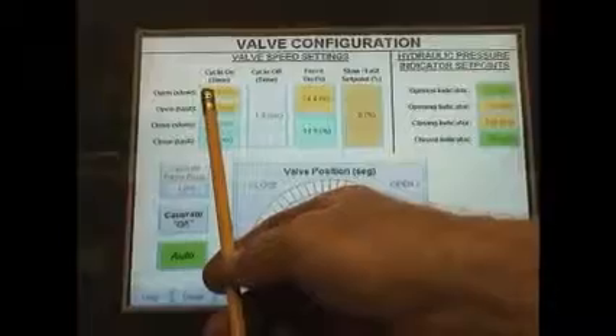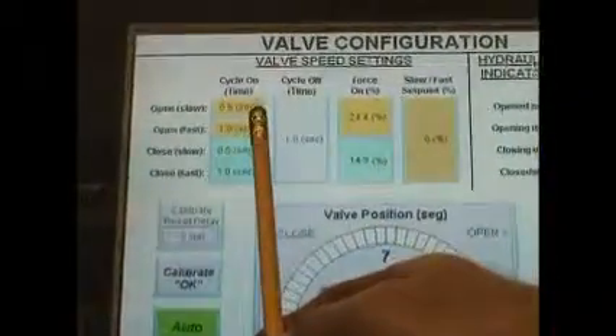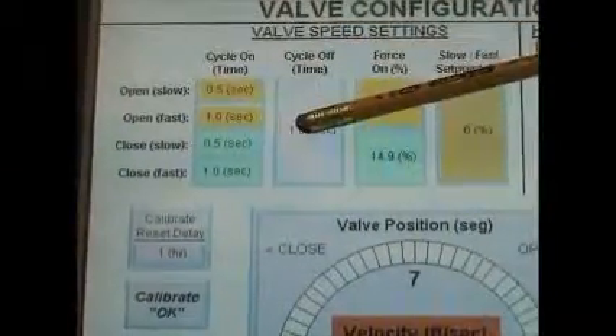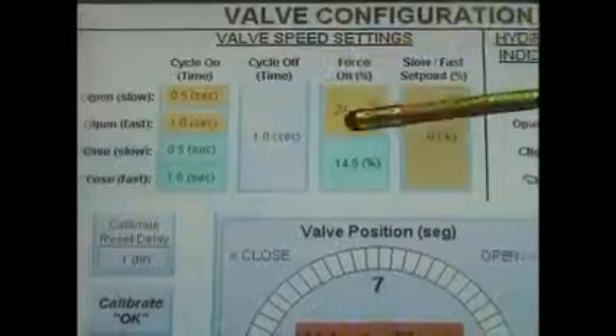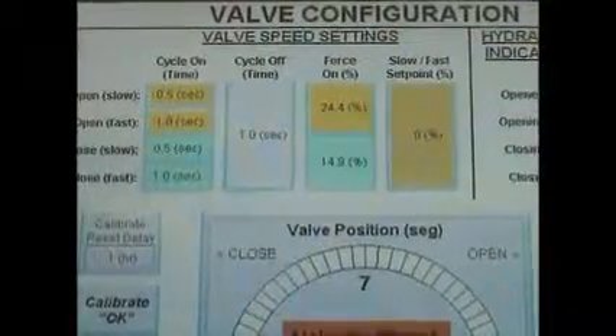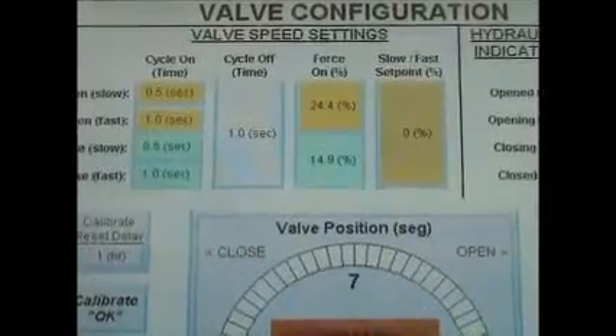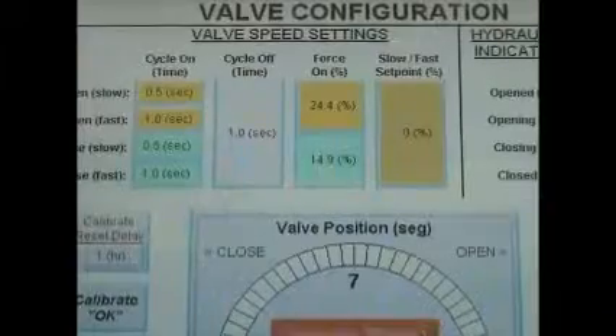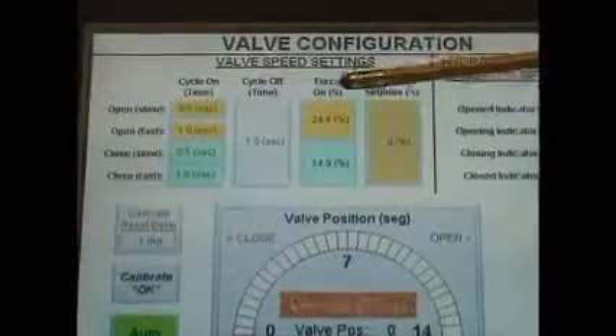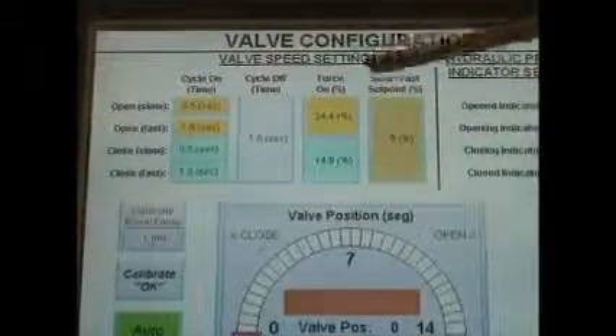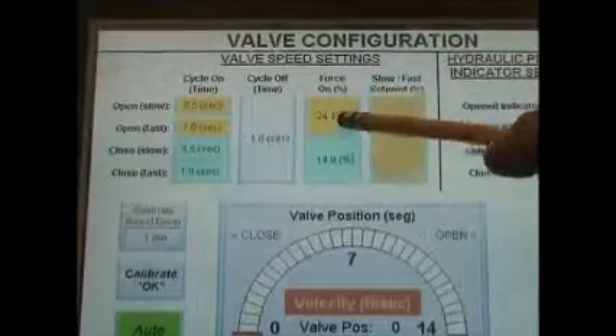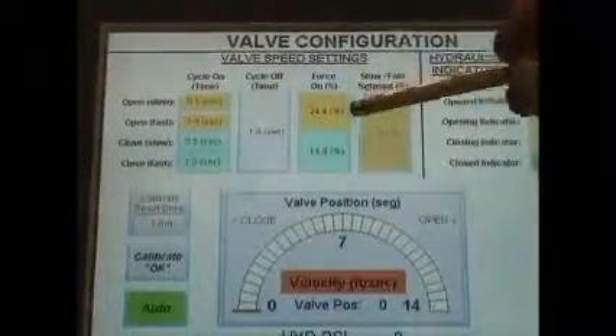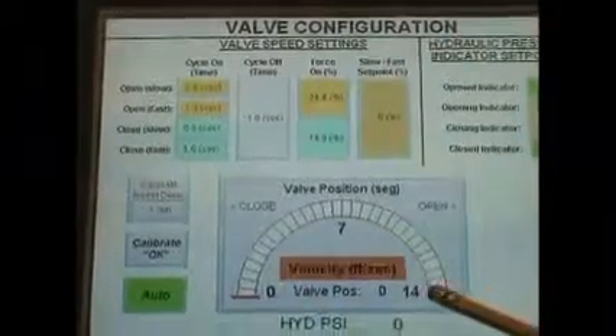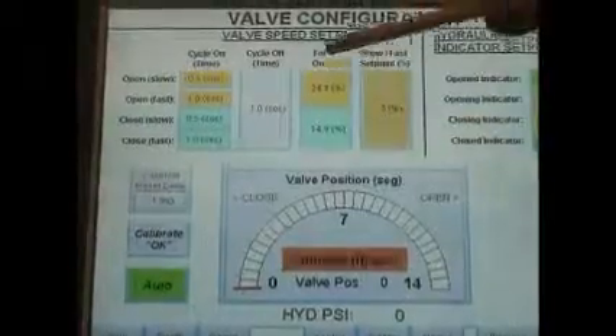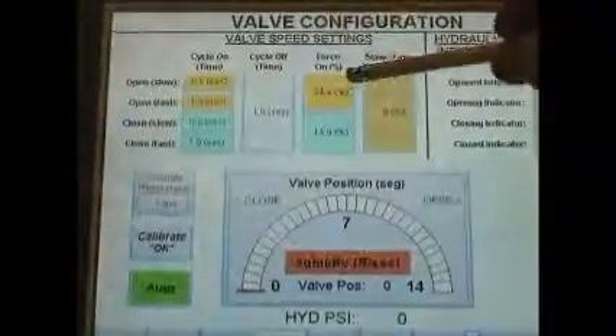The valve, when it opens up for 1/2 of a second, and then it stops. Our cycle off time is for 1 second, and we are opening at 24.4% force. In other words, the voltage to our open coil is getting 24.4% of the total voltage capable of opening the valve. If we want the valve to open a little slower, we are going to decrease our force percentage. Right now our force percentage is 24.4. Let's say we want to get more segments. We want this to be maybe 17, 18 segments, so we're going to give it less force each time the valve opens. So we're going to change this to 22, for example, and hit enter.